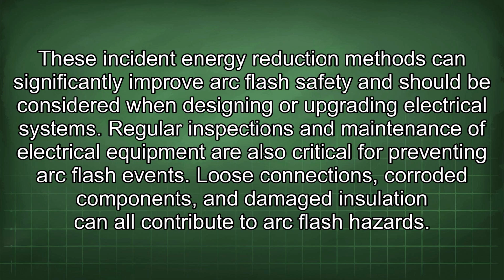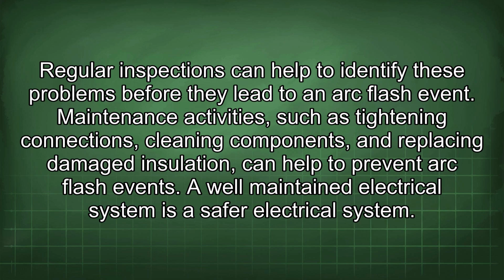Regular inspections and maintenance of electrical equipment are also critical for preventing arc flash events. Loose connections, corroded components, and damaged insulation can all contribute to arc flash hazards. Regular inspections can help to identify these problems before they lead to an arc flash event. Maintenance activities such as tightening connections, cleaning components, and replacing damaged insulation can help to prevent arc flash events. A well-maintained electrical system is a safer electrical system.